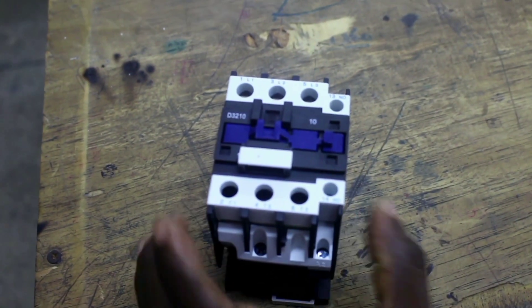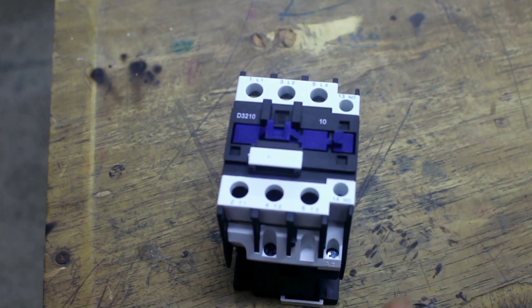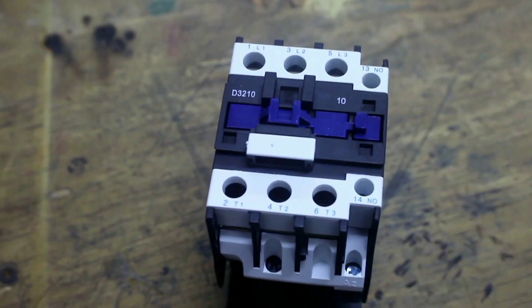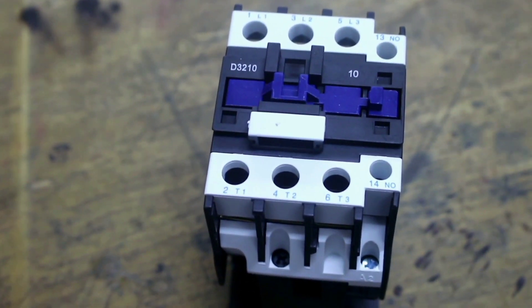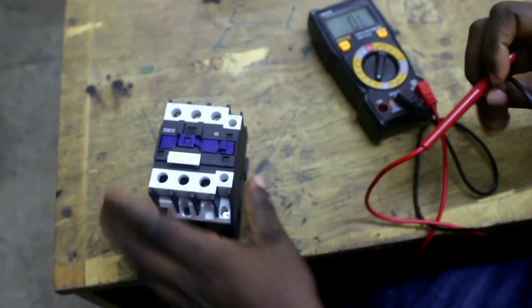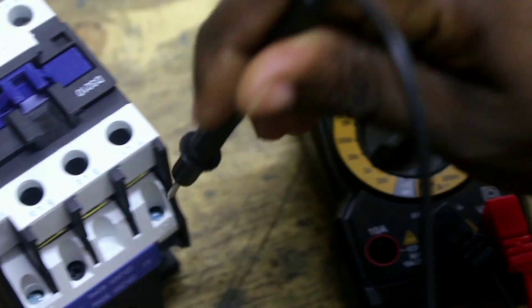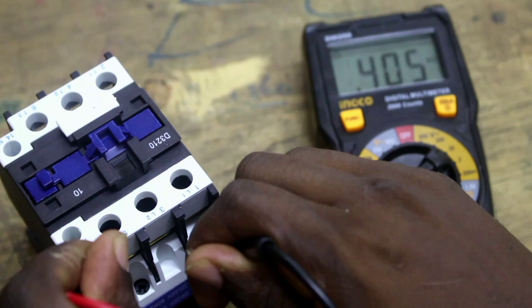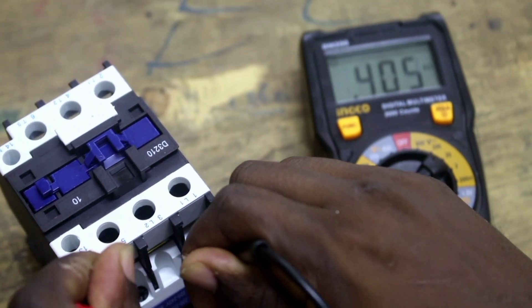Before you connect your electromagnetic contactor to a circuit, the first test is to check the resistance of the coil. We measure it from A1 to A2 — the start and end of the coil. Set your multimeter to ohms and measure. The resistance of the coil is 0.405 kilo ohms.